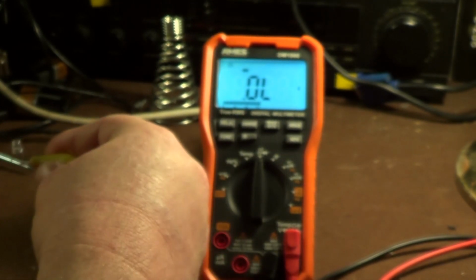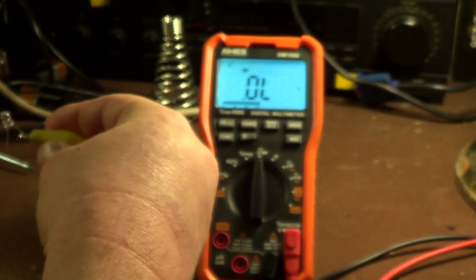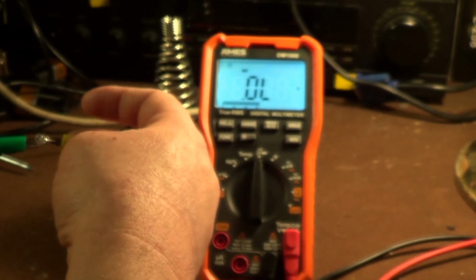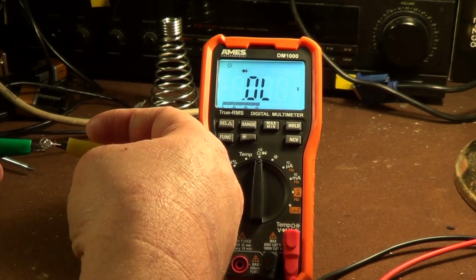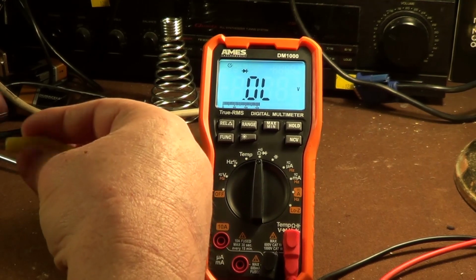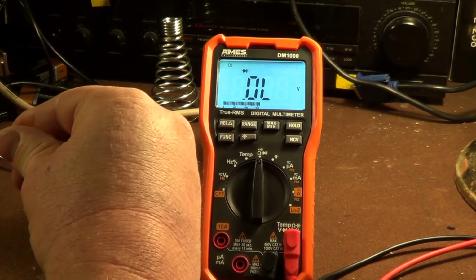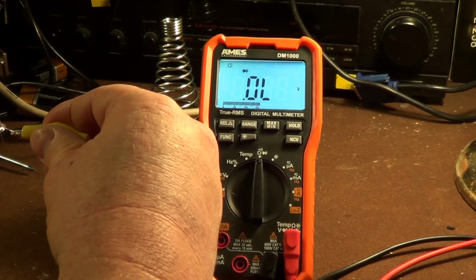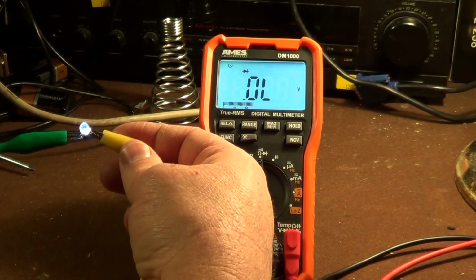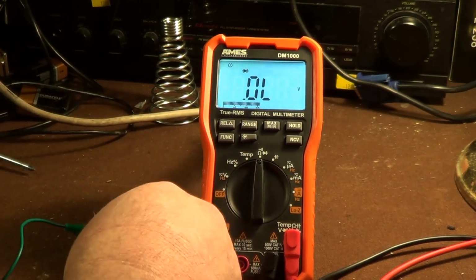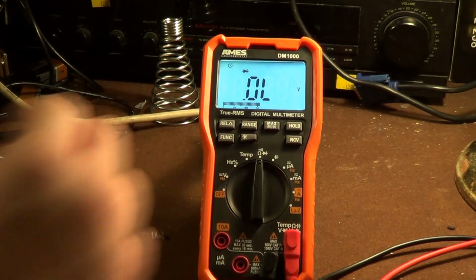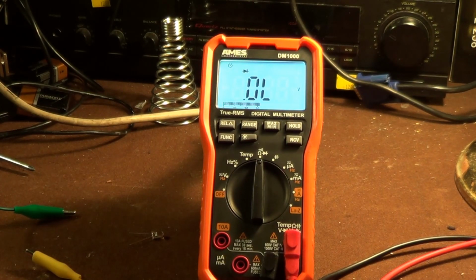And of course you can tell that the diode is good because it is illuminated. Likewise, you could reverse the polarity on it, verify that it's not shorted, though it certainly shouldn't be if it lit up, because the electrical energy would take the path of least resistance. Though I certainly haven't seen every failed diode in the world, but now that the polarity is reversed, the diode is not lighting. So even if you don't get a value out of the Ames Instruments meter, you can at least illuminate the diode and should be able to ascertain whether or not it is good. This test unfortunately wouldn't be much use for things like higher voltage Zener diodes and things along those lines, which appear to be out of the realm of this meter's capabilities.